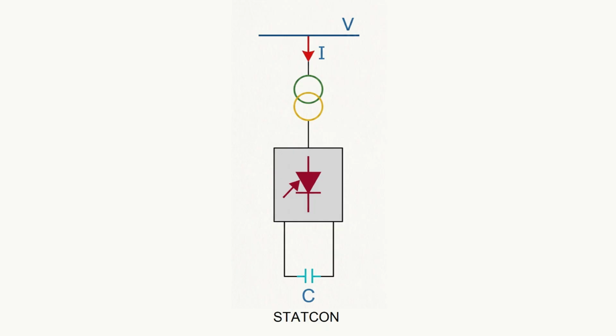STATCON is called a Static Synchronous Condenser because its characteristics are similar to conventional synchronous condensers, but without moving parts, and that is a huge advantage, because moving parts mean maintenance. Moving parts mean wear and tear. Moving parts mean mechanical losses. STATCON avoids all these problems. Now let us understand its construction carefully.